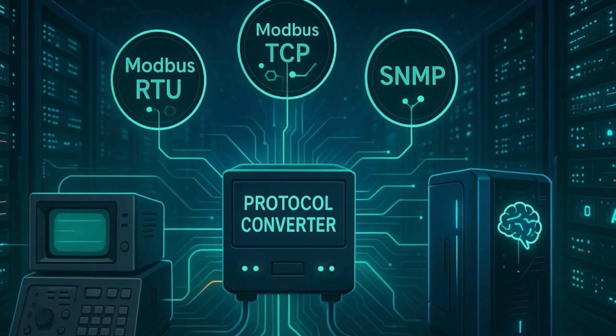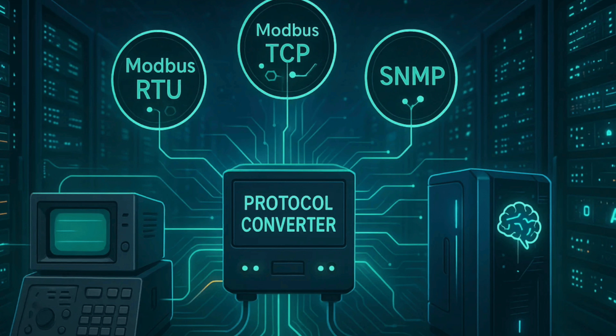And DCIM helps achieve this by pulling in data from different management systems, right? You mentioned BMS. Exactly. DCIM gains this comprehensive visibility and enables intelligent energy management by integrating data streams from building management systems, or BMS, which typically control environmental aspects like HVAC (heating, ventilation, air conditioning), and electrical power management systems, or EPMS, which specifically oversee the entire power infrastructure within the facility.